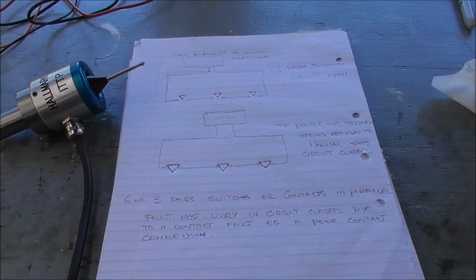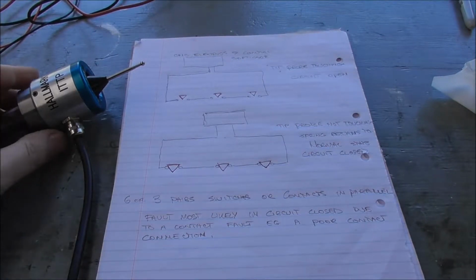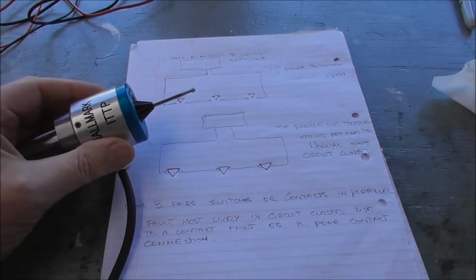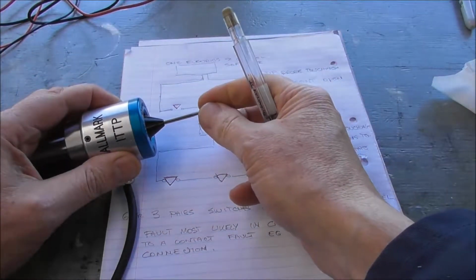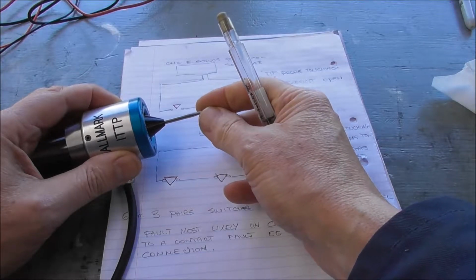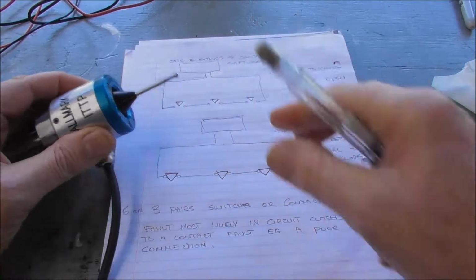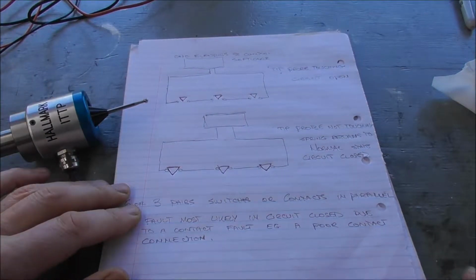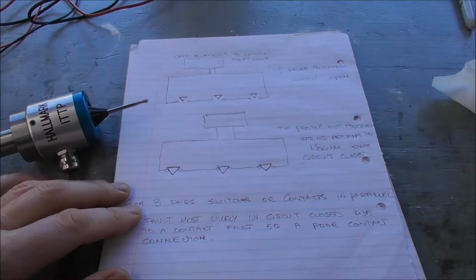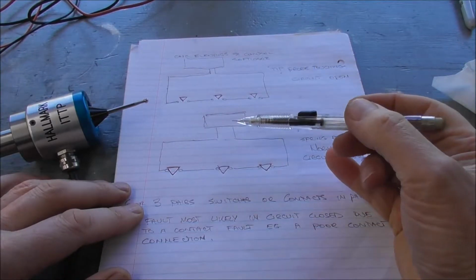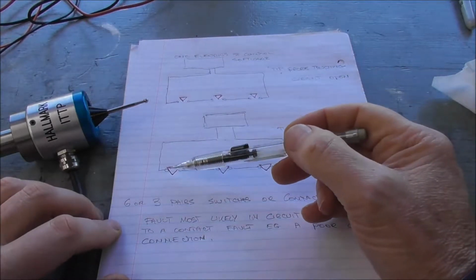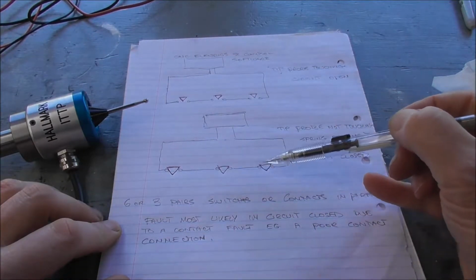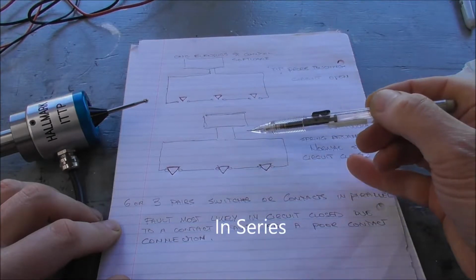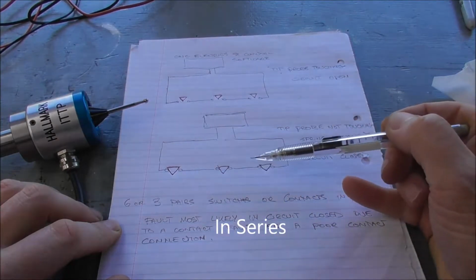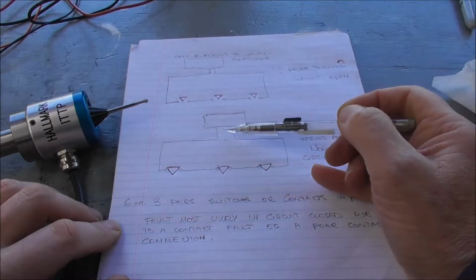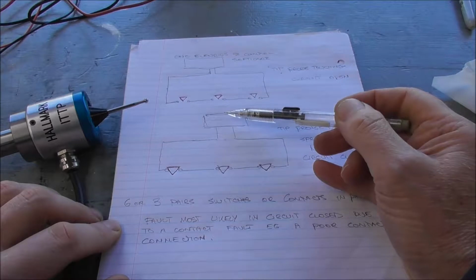Okay, well, let's go into the electrical circuit a little bit more deeply. If you want to test the probe, normally you just plug it into your machine and move the probe tip and watch in the status to see that it's tripping okay. But let's say you want to test it off the machine as part of a troubleshooting process. Let's just look at the circuit. It's a very simple circuit. There are 6 or 3 pairs of switches, or contacts if you like, and the circuit goes through those switches or contacts and returns to the CNC machine electrics and control software.